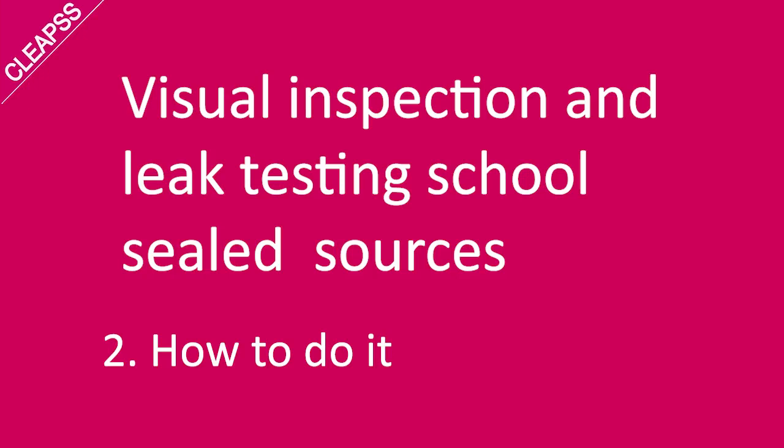The second part of this video explains the way to carry out the inspection and leak testing. You need to wear a lab coat and disposable gloves because of the slight risk of detecting contamination. However, a leak of radioactive materials is rare. The visual inspection tends to reveal any degradation well before any leak of materials.